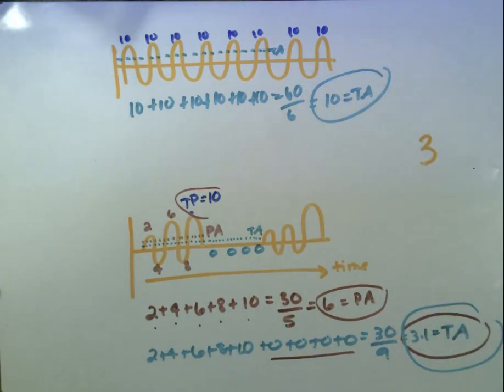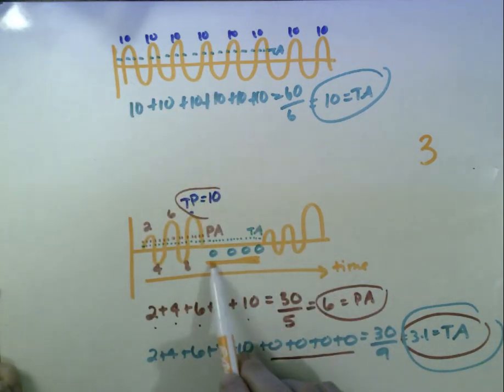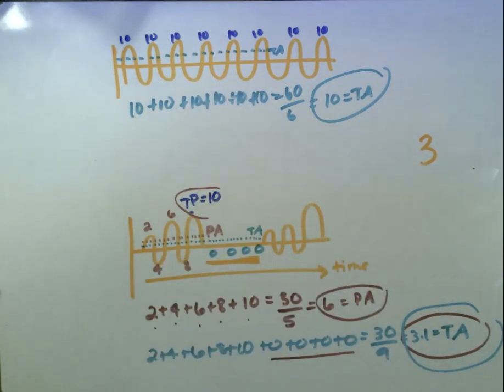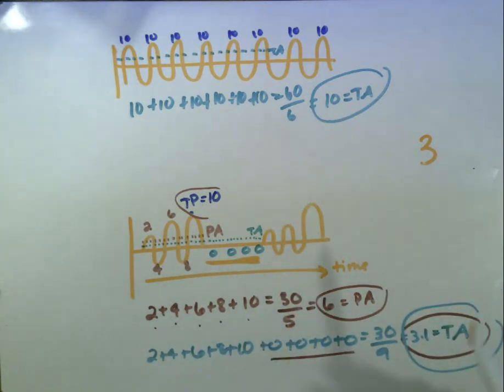And so the short of the answer is that the continuous wave never has this off time here. And because it never has that off time, it just ends up being a higher value because we're not averaging in a bunch of zeros where there's actually sound beams still occurring in the continuous wave. So a continuous wave with the same SPTP as a pulse wave will have a higher temporal average than the pulse wave.